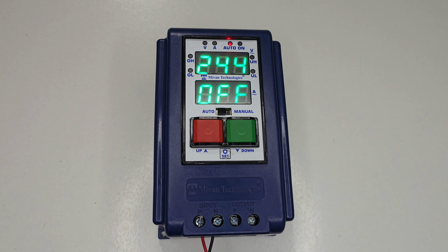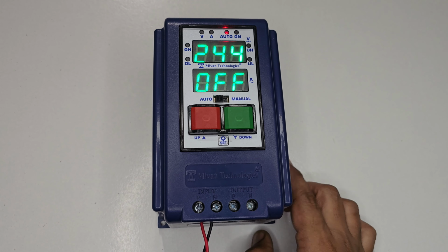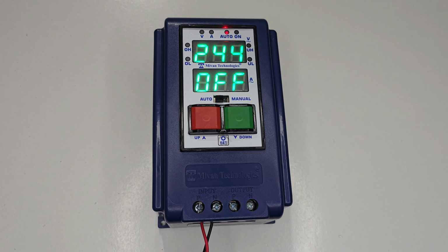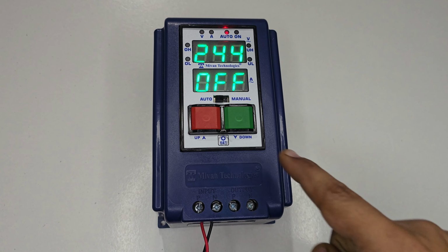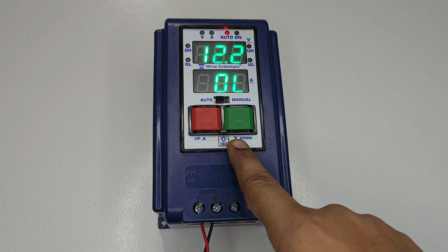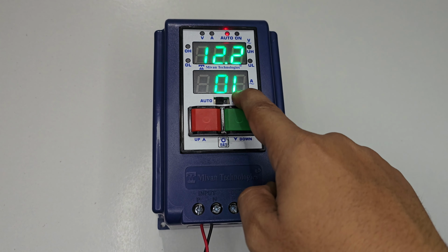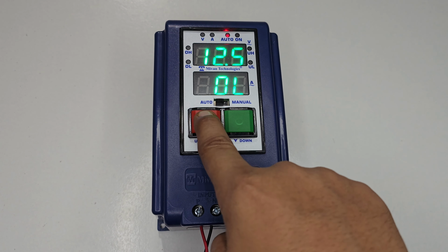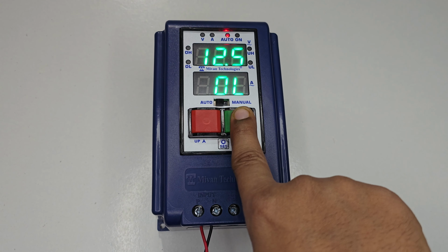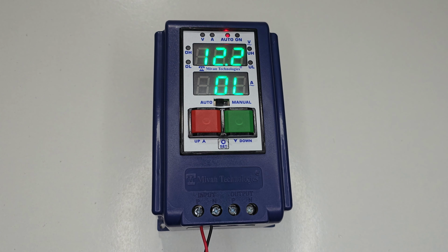Now I'll show you how to program the device. First I'll show you how to set the overload current. To set the overload current, first press the set button. Here you can see the overload current option. By pressing the up and down key, you can adjust the overload current. Set the overload current according to your motor and press the set button to store the value. Normally, the overload current value will be 25% higher than the load value.